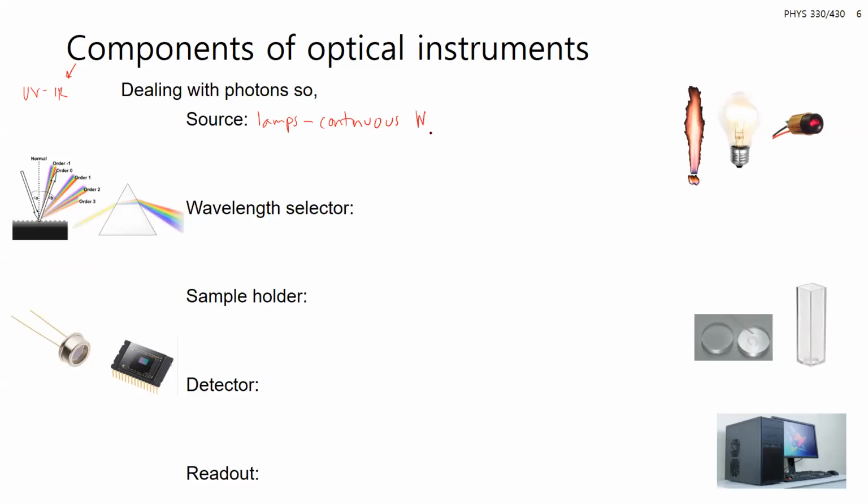And there's lamps like a tungsten lamp where you're heating up a tungsten filament, and that's going to have black body radiation. You can also think of xenon or other halogen lamps where you pass a current through there and it emits light from those electronic transitions. There's also deuterium or hydrogen lamps that again, passing current through there will excite it, it'll emit light, and these will work in different ranges of the electromagnetic spectrum.